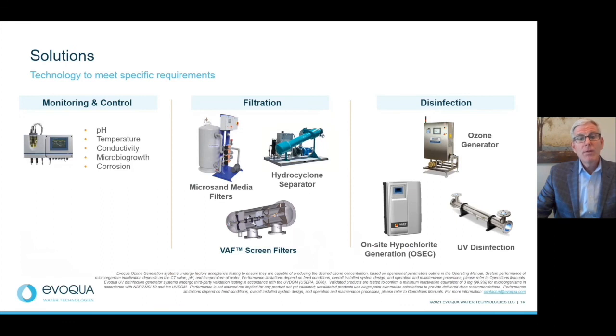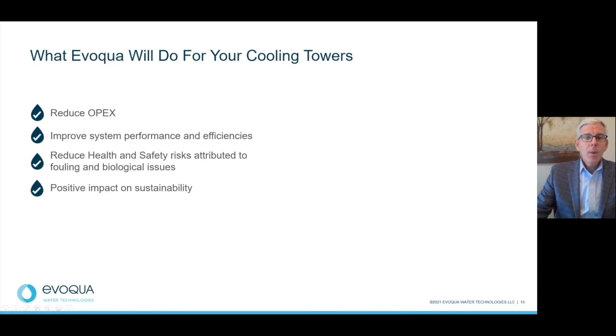Now, while I only highlighted 2 of Evoqua's technologies that can reduce the amount of chemicals needed to treat your cooling water system, we have other sustainable solutions, such as ozone and UV, that could potentially eliminate the delivery of certain consumable chemistries altogether. We also have a platform of monitoring and control devices to ensure that the reduction of chemistry doesn't mean a reduction in performance. I hope I was able to provide some key actions that you can take in reducing the amount of chemicals needed to protect your cooling water system, which will improve system performance and efficiencies, leading to lower operating costs, but perhaps more importantly, help reduce health and safety risks attributed to the transportation and storage of hazardous chemicals.